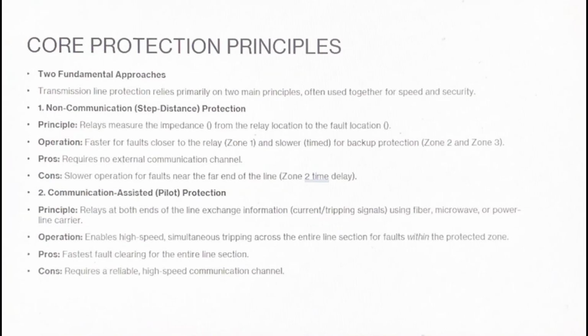Next slide is about the core protection principles. The goal is to contrast the two main design philosophies, distance versus pilot. Transmission line protection relies on two fundamental, sometimes competing approaches. One relies on self-measurement and the other relies on communication. First is non-communication, step distance protection. This is the self-contained approach. The relay only looks at local voltage and current measurements to calculate the impedance. Because impedance is proportional to distance, the relay can tell how far away the fault is. The drawback is the time delay required for backup zones, which we will be discussing next.